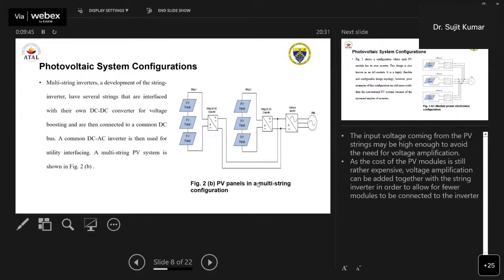Now we have PV panels in a multi-string configuration. In the multi-string inverters, you can see here, this is my DC-DC multi-string with a DC-DC converter, another DC-DC converter, and then we have the common inverter. You can see from this figure that there are several strings that are interfaced with their own DC-DC converter. Each string will have its own DC converter for voltage boosting, and the boosted voltage is delivered to this common DC bus.